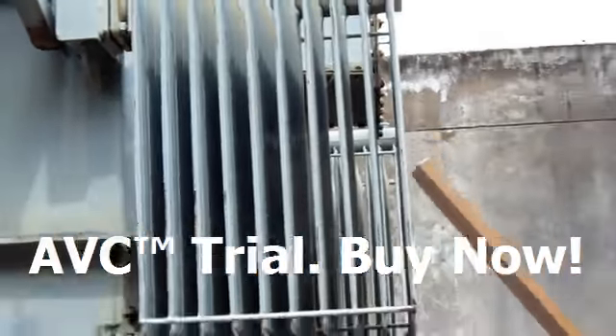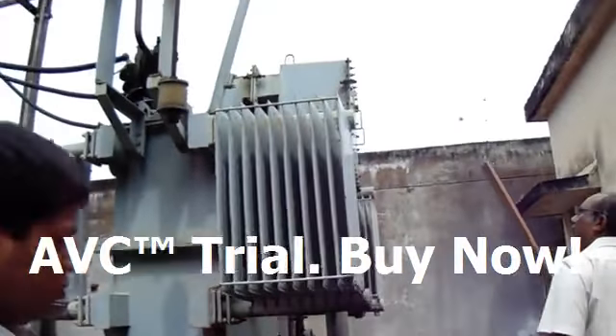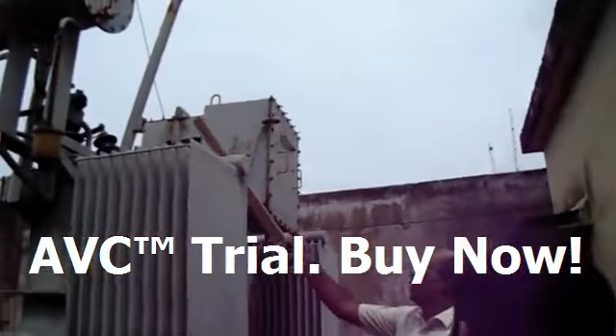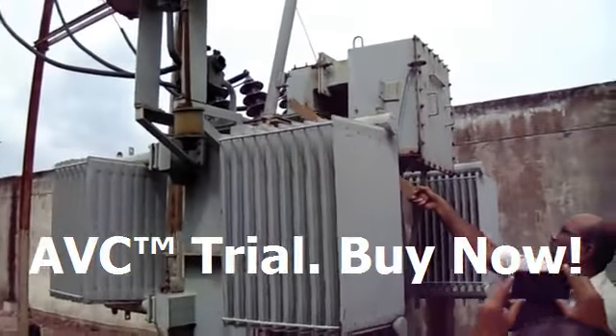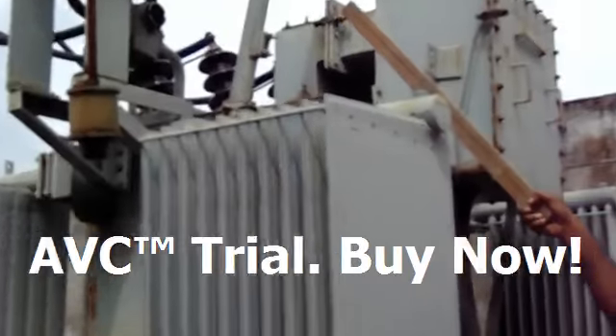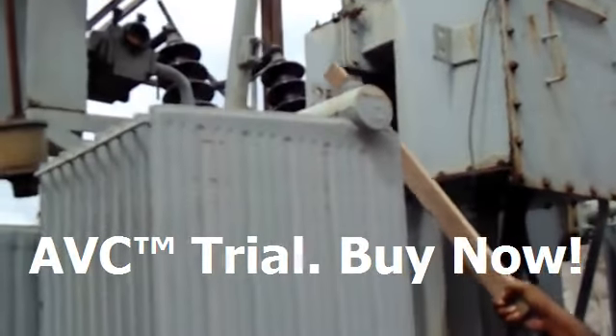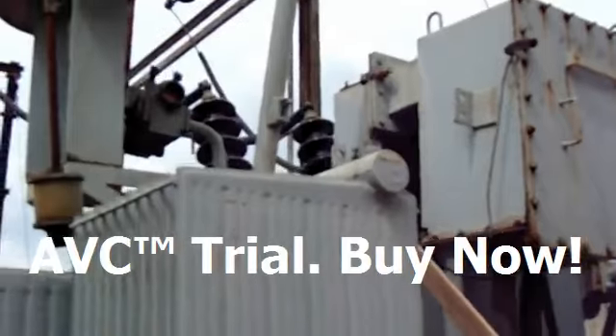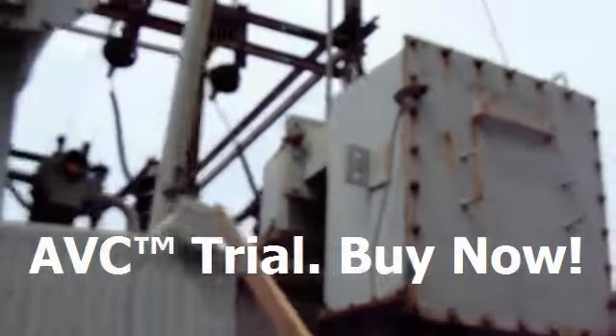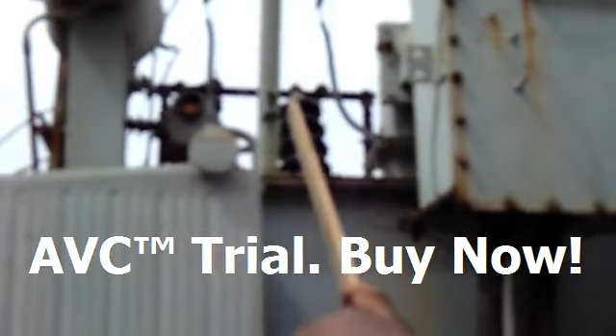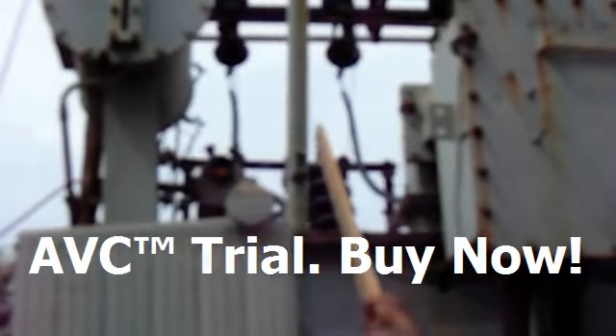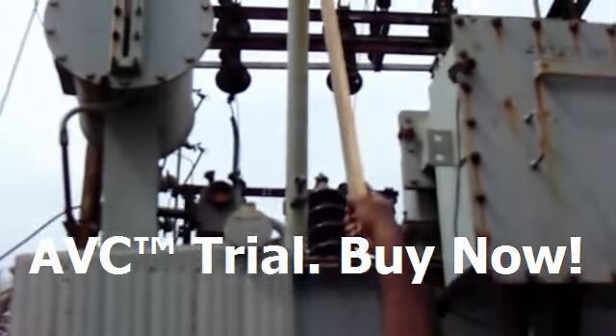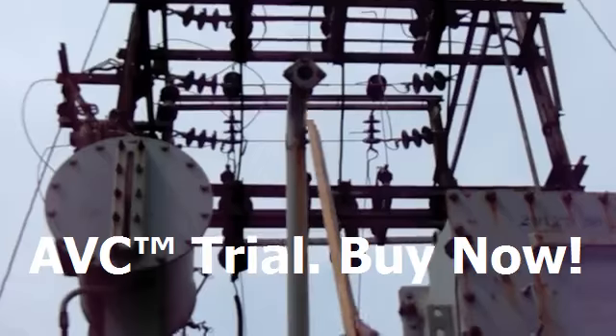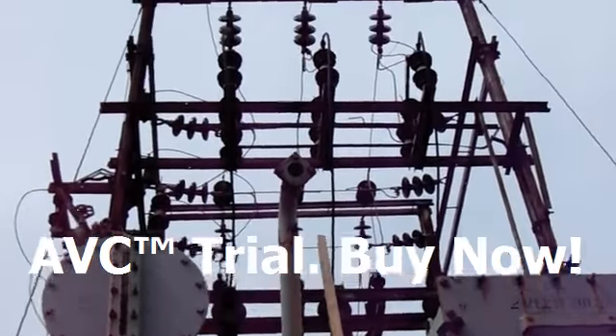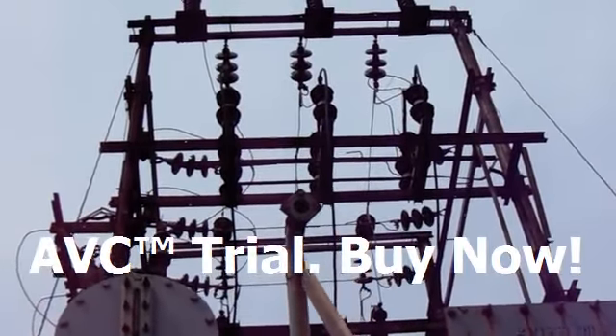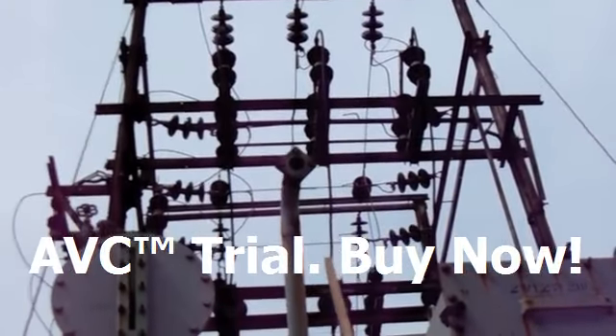Then the other important thing is this one, the pressure vent. This is the pressure vent. Due to internal faults in the transformer, the oil will get heated up. There will be heavy pressure, just like your pressure cooker, and if it exceeds and no protection is given, then through this pressure vent the gas will break that glass. You can see that there is a glass at the top. It will break the glass, and whatever extra pressure is there will come out from the transformer. Therefore, there will not be any exploding of the transformer.